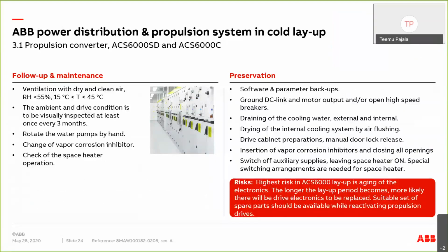Then propulsion converters. ACS 6000 SD, ACS 6000 C mentioned. Also, it can be ACS 800, 880 low voltage drives. Basically, the same considerations apply also for those. So water pumps need to be rotated every now and then. In the preservation side, you can see that the cooling water should be drained out of the system. And the cooling system should be cleaned by flushing air so that there is no dust or anything around. And also external water, LD water circulation should be drained.